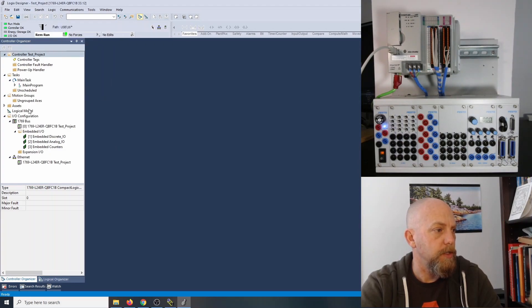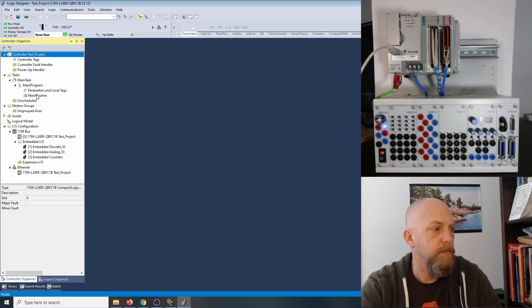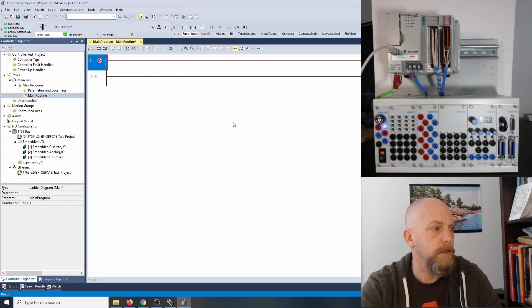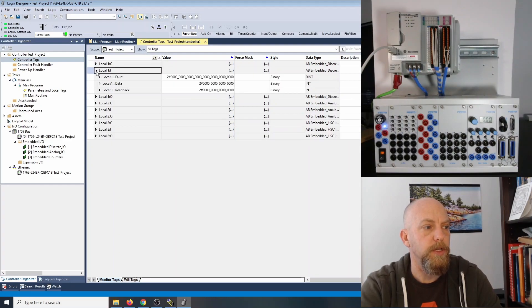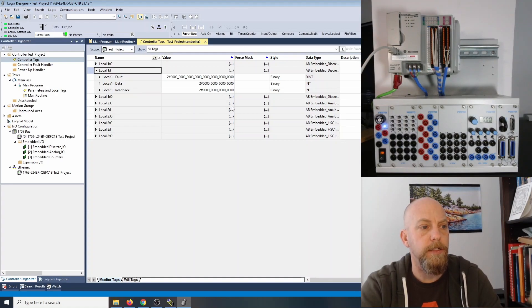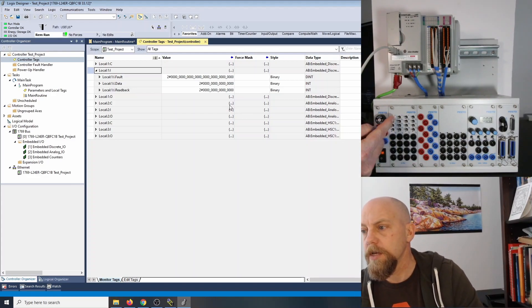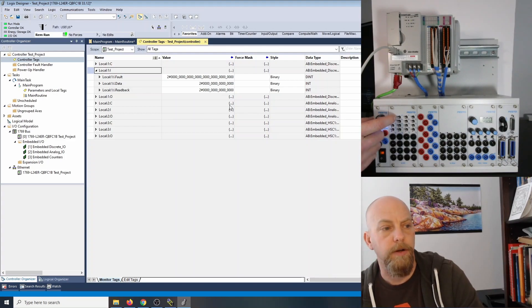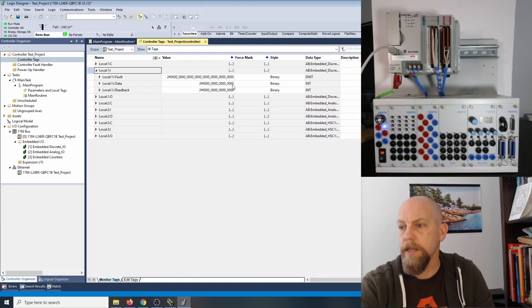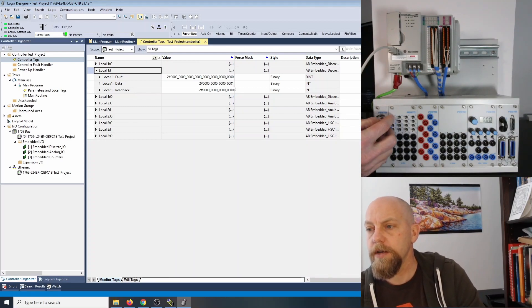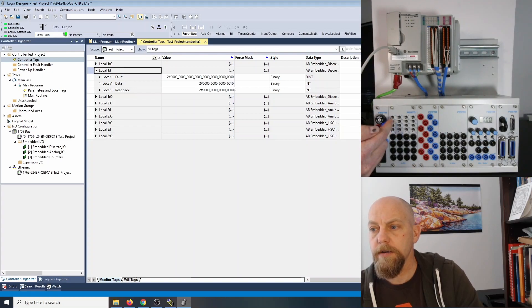Let's look at our inputs. We'll go to Main Program, Main Routine. Then up in the top left, we'll double-click on Controller Tags. I want to look at my local inputs — Local:1:I for inputs. I'm going to flip each sequential input. This is input zero — we should see that change state. You can see that changes to a one for input zero. Input one is next, then input two, input three.